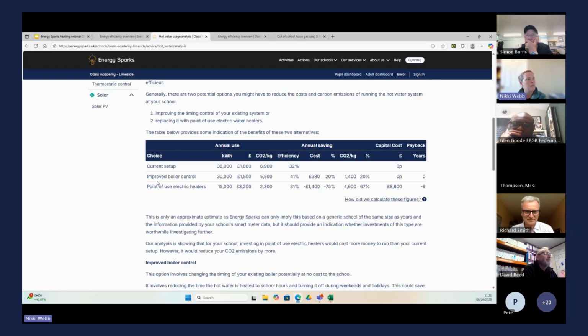We look at the difference between improving your boiler control, reducing the hot water circulating around your school all the time, or installing point-of-use electric water heaters — including the investment needed and the payback time. For some schools this analysis gives a really good payback, maybe just a year or two, simply by reducing the gas used to heat hot water. For this school, though, the payback isn't going to be as good.